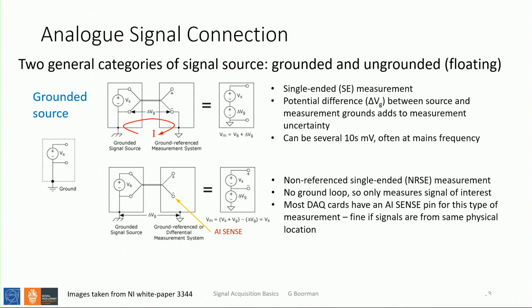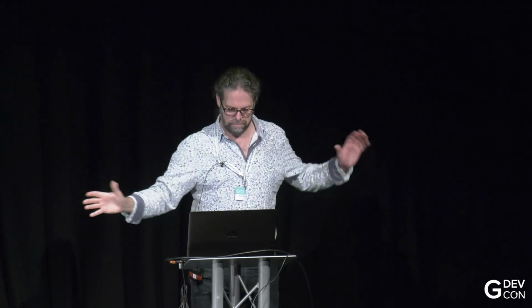It's very useful because you've got your grounded signal source and your measurement system is still grounded. But the negative side of the signal source goes across to this AI sense, which is not grounded; it's isolated from ground. That means your signals can actually be measured and you don't get any ground loop, because you've broken the loop. That's what you've actually got to do. Most of these devices only have one AI sense pin, so all of your signals have got to come from the same source. There are not multiple AI sense pins. So it's okay if all your signals originate from the same place, not so good if you've got them coming from disparate sources.